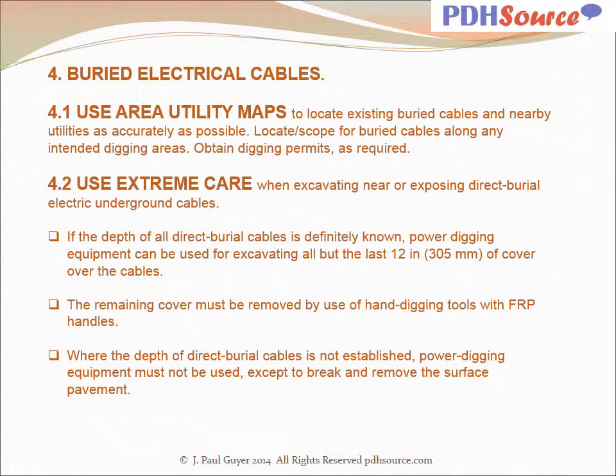Use extreme care when excavating near or exposing direct burial electric underground cables. If the depth of all direct burial cables is definitely known, power digging equipment can be used for excavating all but the last 12 inches of cover over the cables. The remaining cover must be removed by use of hand digging tools with FRP handles. Where the depth of direct burial cables is not established, power digging equipment must not be used except to break and remove the surface pavement.